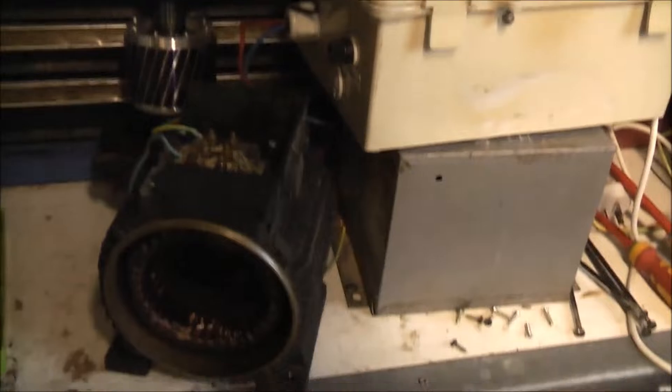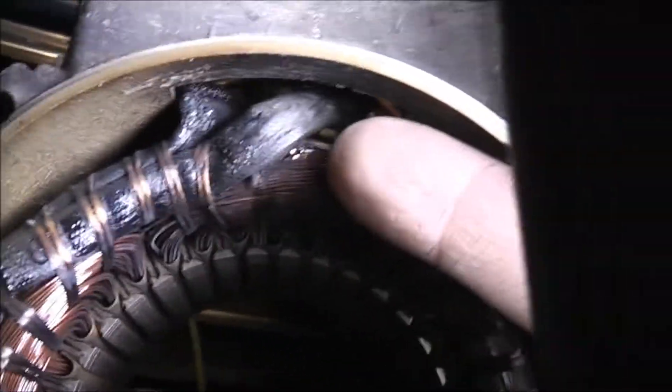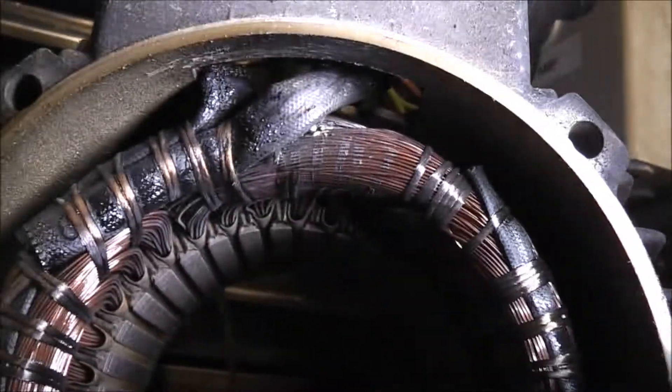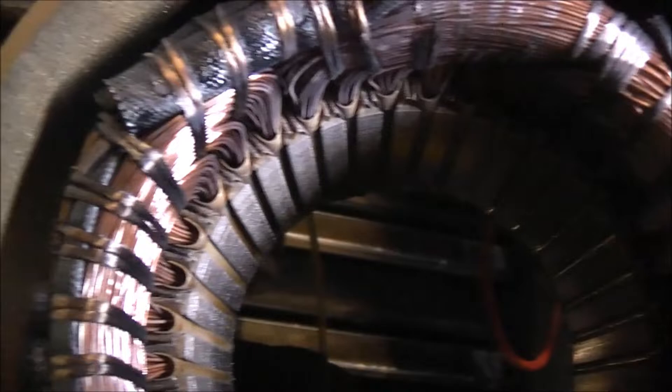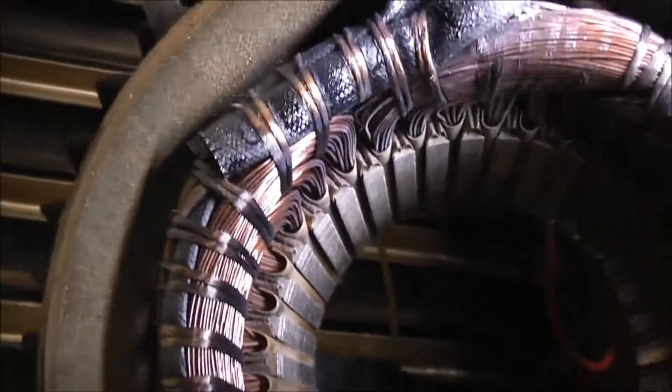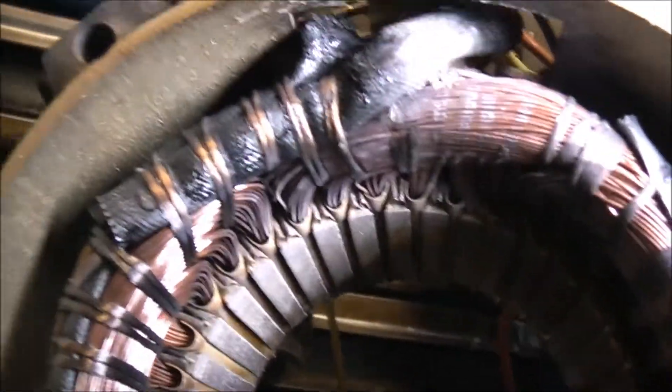That sort of failed as well. Just because I passed the megger test, it only tests it for a short-to-earth. There's actually a pop on the windings. I've got to get the parts off this motor. I've got a popped winding there, blew like a fuse. I could dig them out and solder them up and insulate them again.